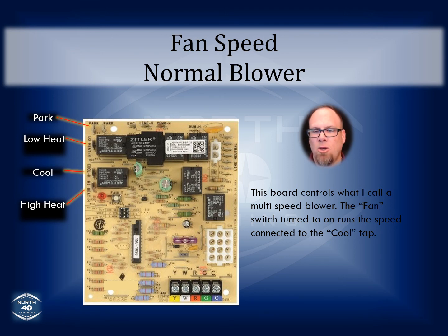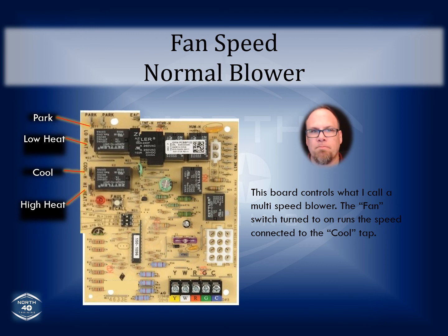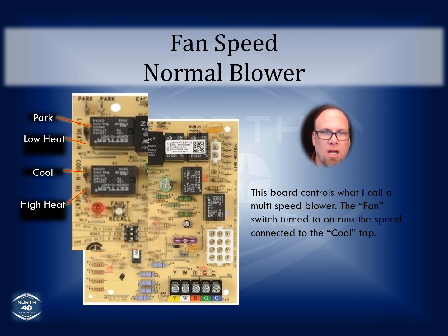So as you might guess, what I will do is I'll put my manometer in those two penetrations, the one before the blower, the one after the blower, and I will go from one fan speed, turn it on, write down the static measurement, pull it off and swap it out with another one on the cool, and then I will go to that one and then write it down, and then I'll swap it out with a different one yet, and I'll go from one to the other on that cool terminal, turning the fan speed on, so that way it's very quick. I'm not using heat or I'm not using cool. I'm just looking at the raw values for the static and the ductwork. That's all I'm looking for, so I can properly set up that blower. Okay, and there's a little bit closer look at what we're talking about.